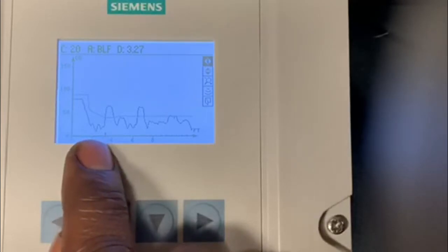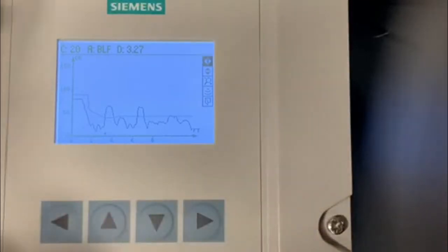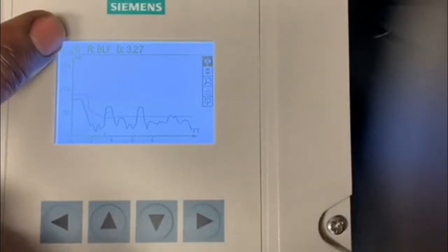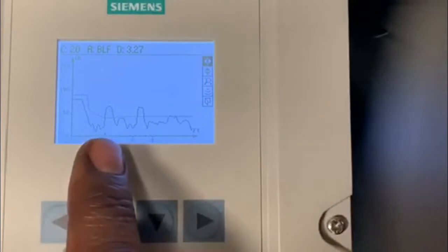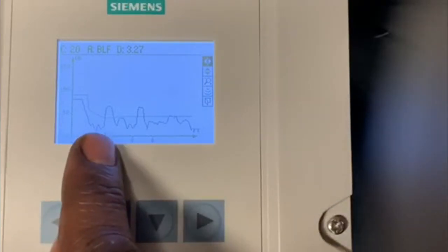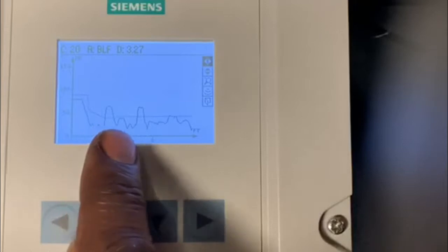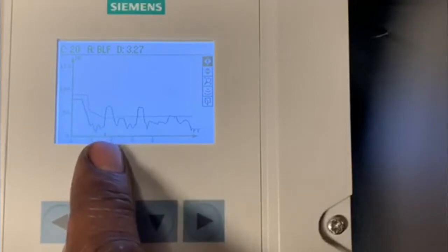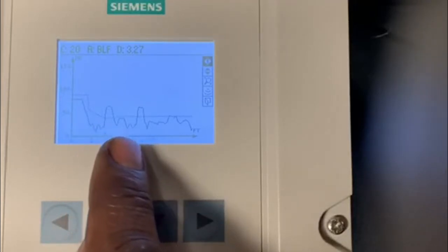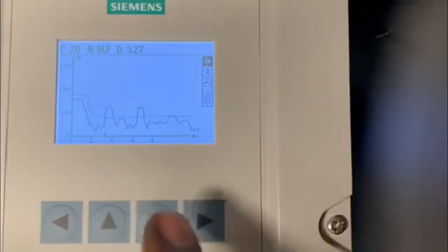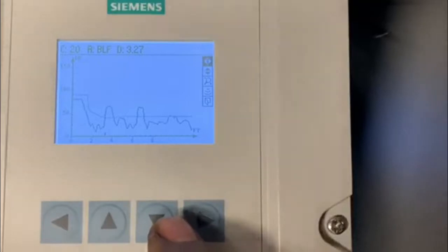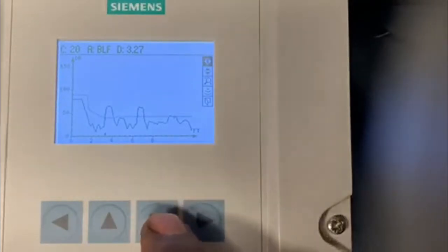One would be by possibly choosing a different algorithm. The A:BLF signifies that we are using an algorithm called best of largest first. So we could possibly use an algorithm that did not include the first parameter. But as you can tell, the two echoes are very similar in size as they cross the dotted line, or our threshold. So let's try the auto false echo suppression.